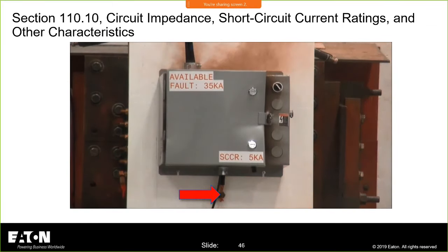We did a few more tests on different types of equipment. So that looks like my shirt after a good Thanksgiving dinner. But you'll notice that the actual fault, we bolted the circuit downstream of this equipment, and it just could not pass through.